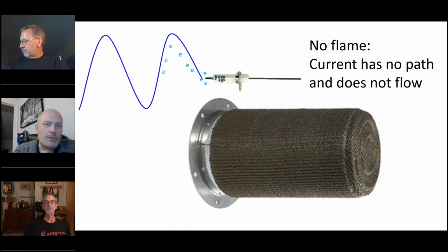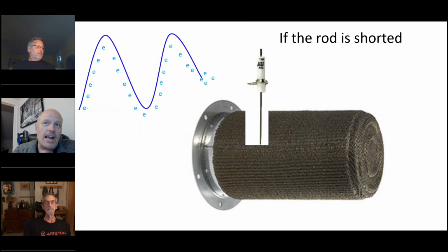So let's jump through this. And the reason we do this rather than just putting a thermocouple or something else is if there's no flame, there's no conductivity. So that means we don't get any electricity forward or backwards. So there's no flame signal. If our flame rod happens to be touching the burner, what's going to happen is all the electrons will exit to the burner. And because metal on metal contact conducts both ways equally, we get all the electrons that we sent out back. So we sent out 100, we get 100 back. The difference between 100 and 100 is 0. So we've got 0 flame signal.